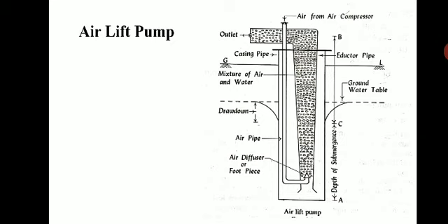Because of this, this type of pump can be used for water which contains mud, silt, debris, etc., because there is no rotation or movement in the parts which are under water. You can even use it for highly acidic and alkaline water. So the airlift pump can be used for any type of water, even polluted water.